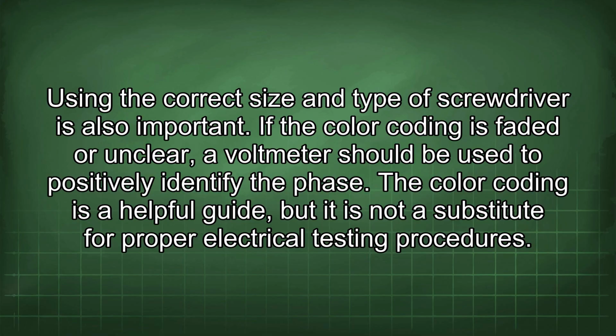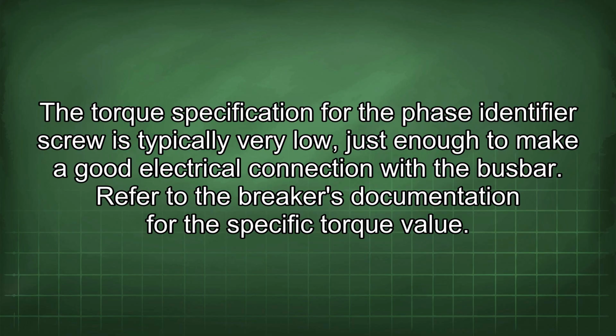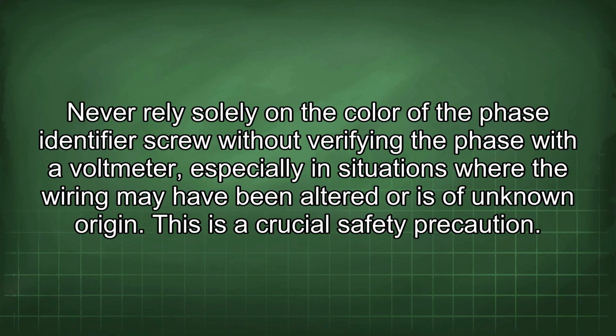If the color coding is faded or unclear, a voltmeter should be used to positively identify the phase. The color coding is a helpful guide, but it is not a substitute for proper electrical testing procedures. The torque specification for the phase identifier screw is typically very low, just enough to make a good electrical connection with the busbar. Refer to the breaker's documentation for the specific torque value. Never rely solely on the color of the phase identifier screw without verifying the phase with a voltmeter, especially in situations where the wiring may have been altered or is of unknown origin. This is a crucial safety precaution.